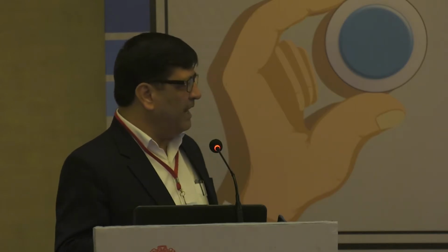The peak load here is about 1500 TR, which you can convert to kilowatts of connected load for a building. Around 3 or 4 o'clock, any building would normally peak. For ages, we've been designing buildings for this peak load, even though it happens for maybe only 3 hours in a year out of 8,760 hours total.